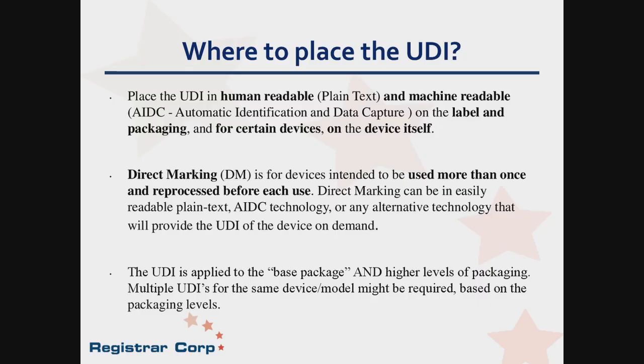Where to place these UDIs? The UDI has to be in human readable part, which are the numbers, and the machine readable part on the label and the packaging, and for certain devices on the device itself. On the device itself, it's called direct marking of a device, and that applies only to devices that are used more than once and reprocessed before each use.